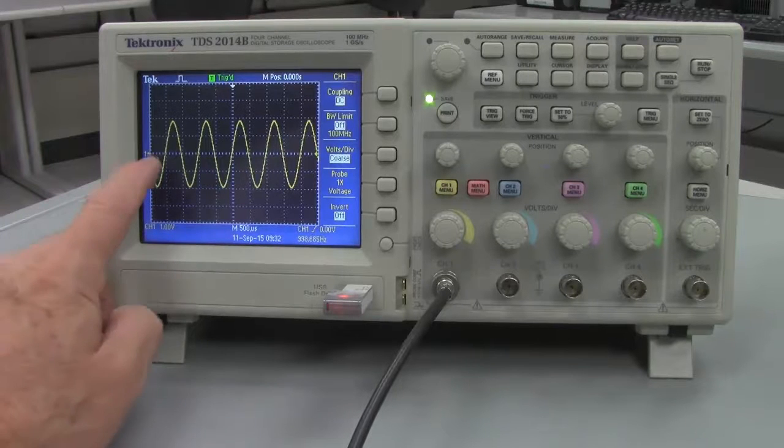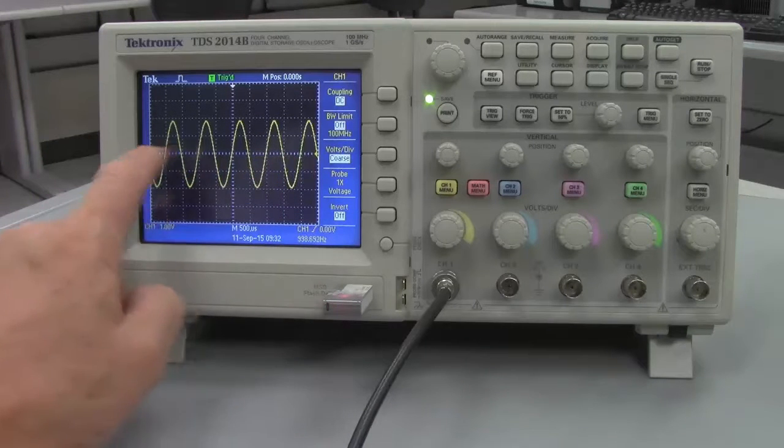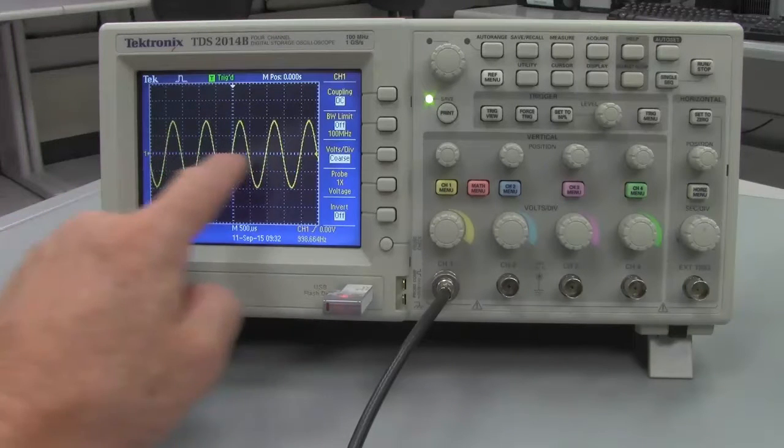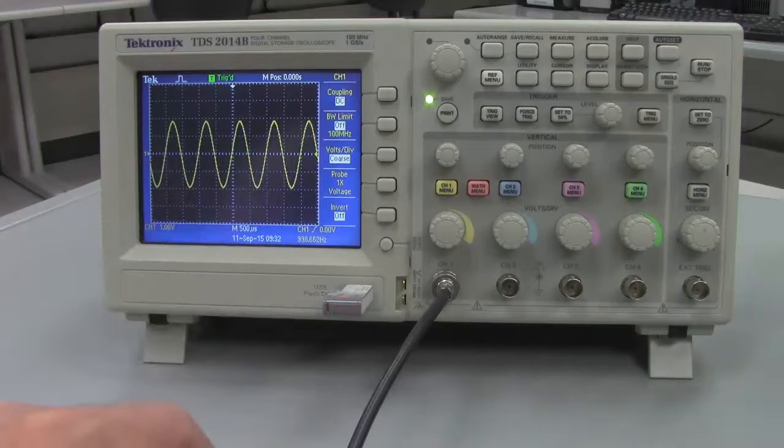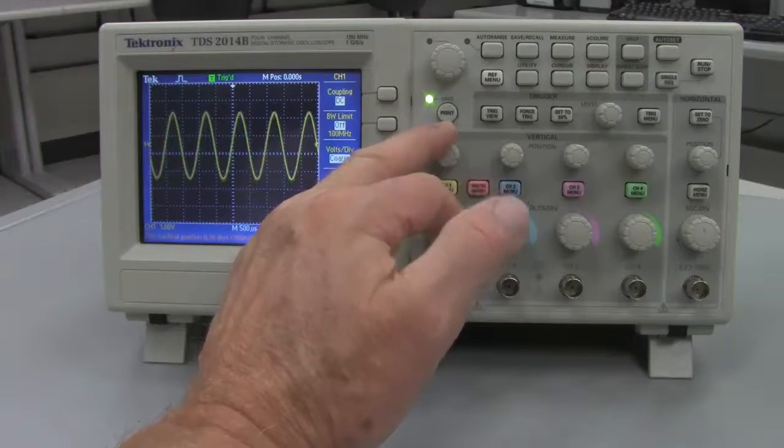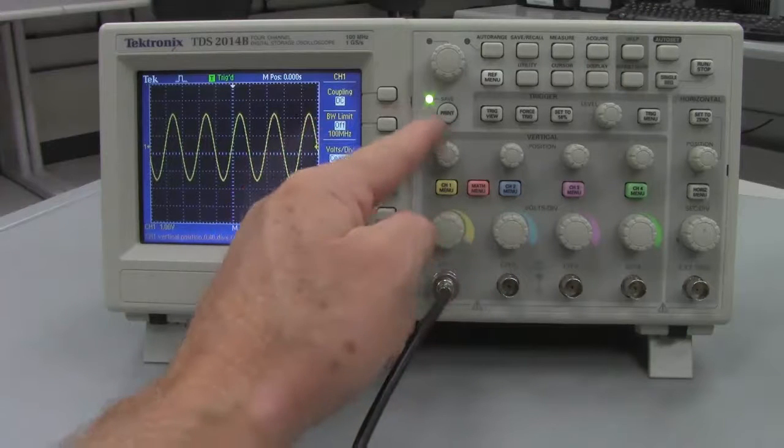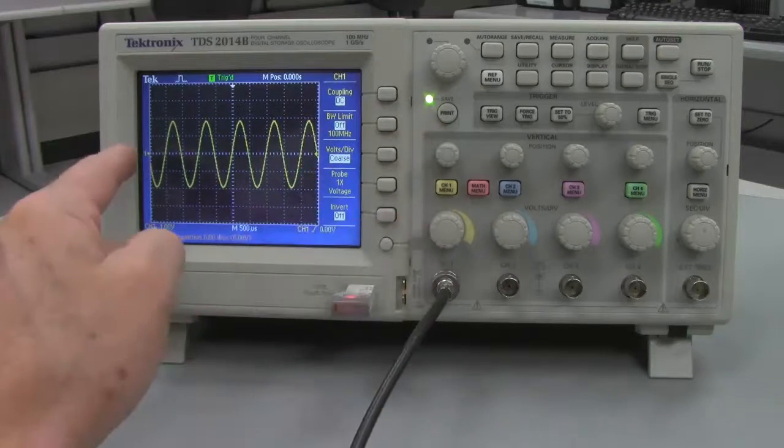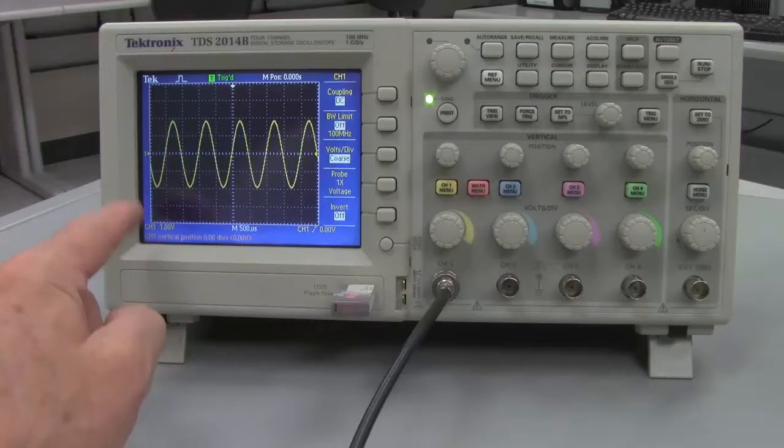Now we see that the signal coming out of the signal generator is only almost 2 volts in the positive direction and almost 2 volts in the negative direction. Now it came up in the default with the center location, the center voltage, or zero voltage, right here at the center line. Had it not, or if we wanted to adjust that, we can adjust the vertical position by turning this knob right there.